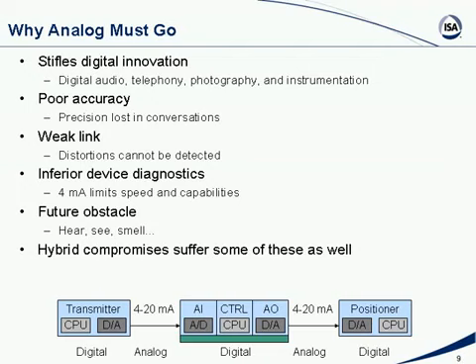Fieldbus enables innovation. Fieldbus has created new classes of instrumentation that never existed before. We have multiple channel temperature transmitters that accept 8 sensors each. We have pump health transmitters, and we have discrete I/O boxes sitting out in the field. So all of this was not possible before. Fieldbus gives us alerts for predictive maintenance. If we have plugged impulse lines and so on, that gets alerted to the technicians, who can look into that before. For example, if the pressure measurement no longer works, that can be rectified.